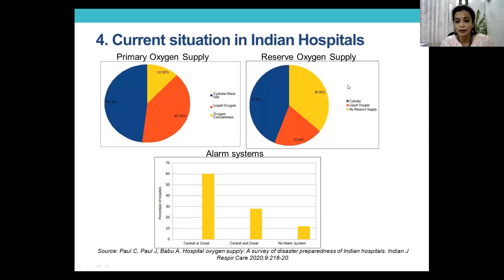Now, for the alarm systems to see how much the pressure is dropping, you need to have central and also zonal-wise alarms. More than 12% of the hospitals did not even have an alarm system to say that the pressures are dropping. So you're actually dependent on the patient becoming sick, and then you decide whether the oxygen flow is there or not. That's actually the problem. This is just to give you a glance of what it is in our country.